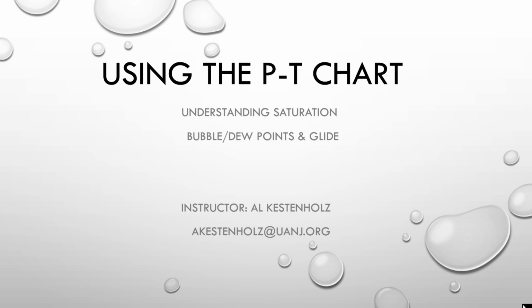410A, we call it near azeotropic, but it only has about a 1 degree, 2 degree glide at the most. And we never really concern ourselves too much with the bubble and dew point of 410A, but it becomes relevant when you're dealing with 404A, especially if you're going to do 407C, which is a replacement for R22. You can have up to an 8 to 10 degree difference in the glide. So we're going to go into that today and go through some worksheets here with this PowerPoint.